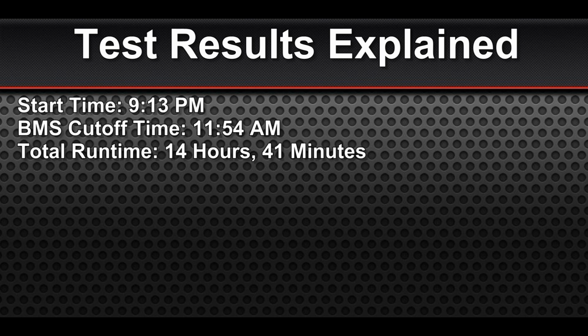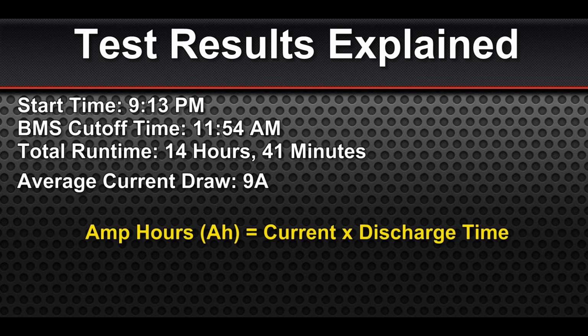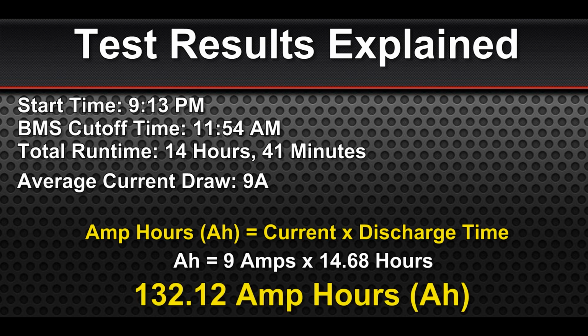Let's talk about what we learned from this test. We started at 9:13 p.m. and finished with BMS cutoff at 11:54 a.m., for a total runtime of 14 hours, 41 minutes. Our average current draw during the test was 9 amps. The formula for calculating amp hours is shown on your screen. Let's plug our known values in: 9 amps times 14.68 hours comes out to 132.12 amp hours out of a 100 amp hour battery. This battery outperformed its rating.